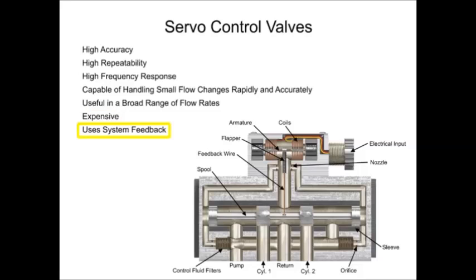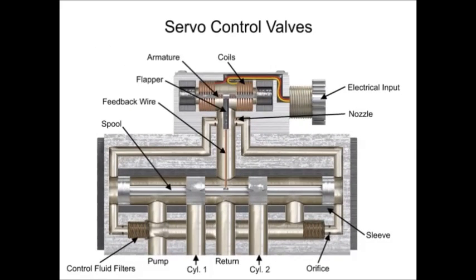The main difference between proportional and servo valve circuit design is that servo systems have a method of feedback that assures that the actuator is doing what the controller tells it to do. Most industrial applications use feedback from electronic linear, rotary, or force transducers. A transducer is a device that produces an electrical signal in direct relation to a position, force, or speed. These devices feed a precise position or speed indication back to an electronic controller via a feedback wire, which in turn adjusts the valve.